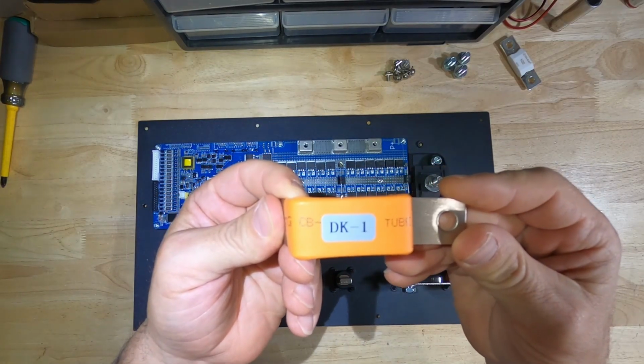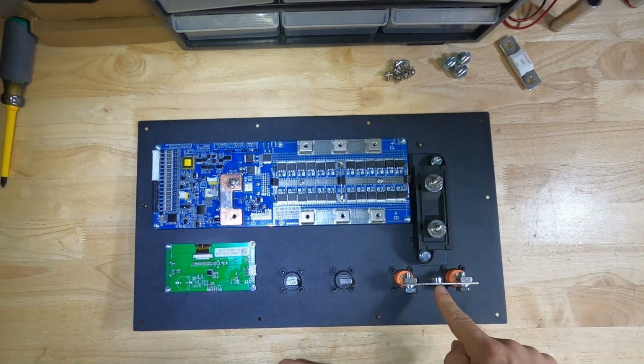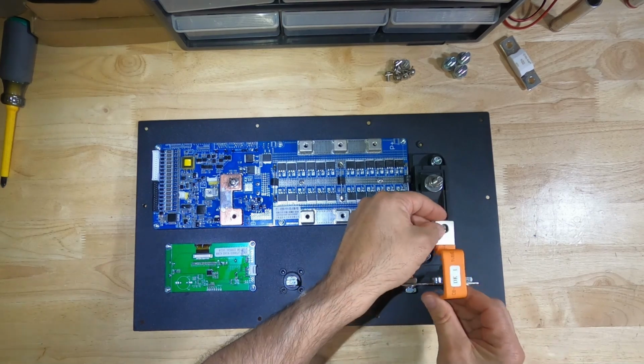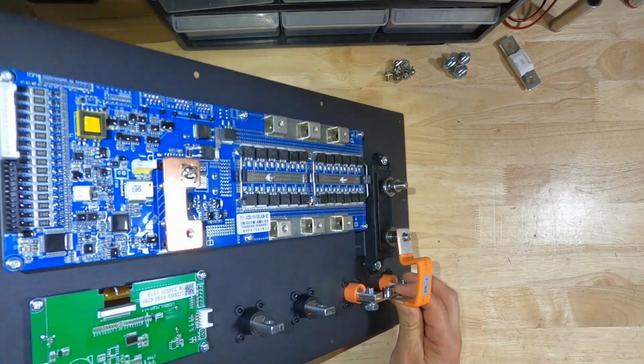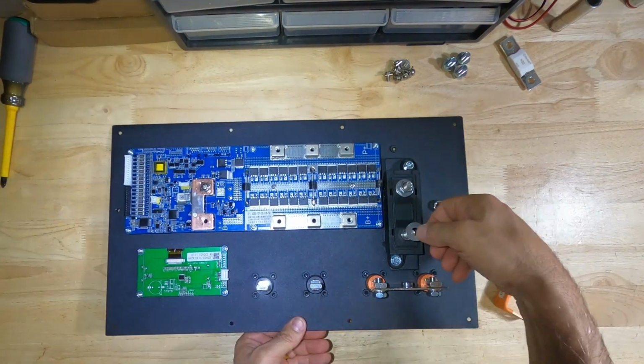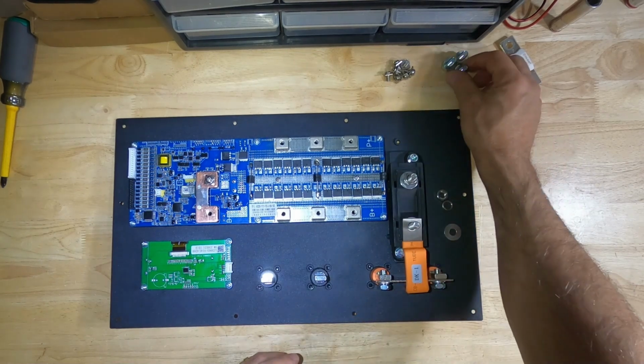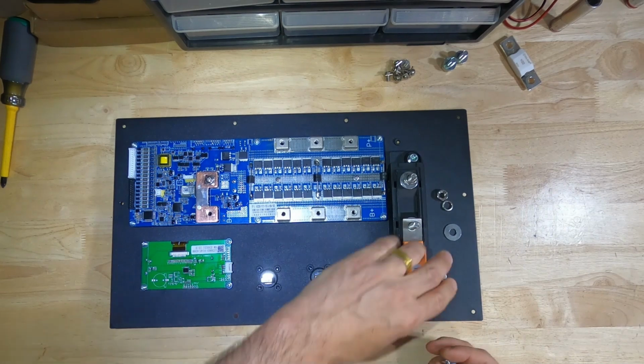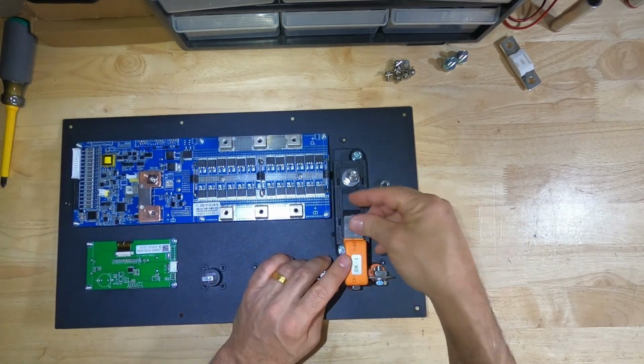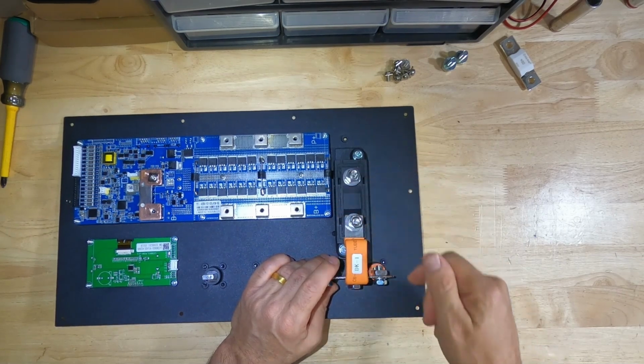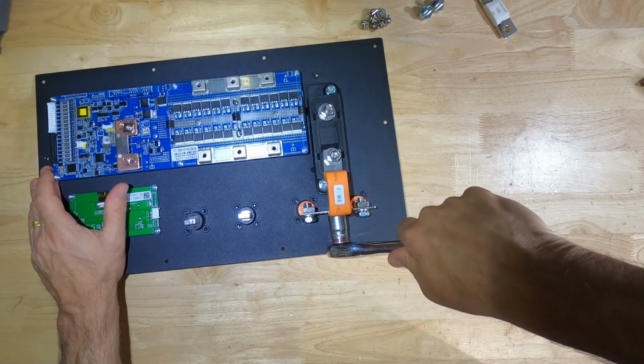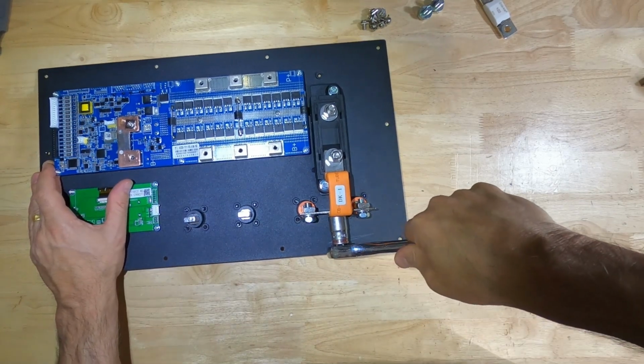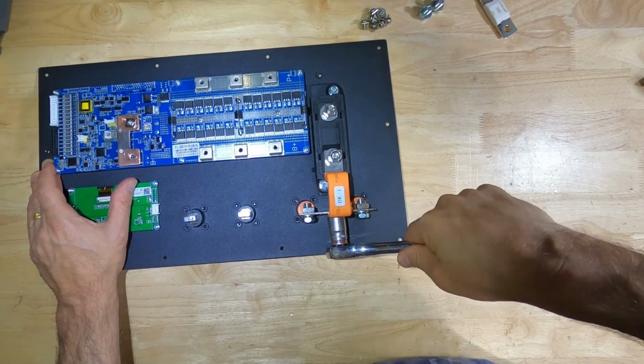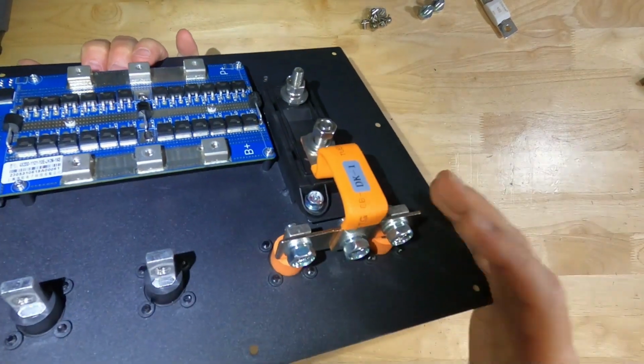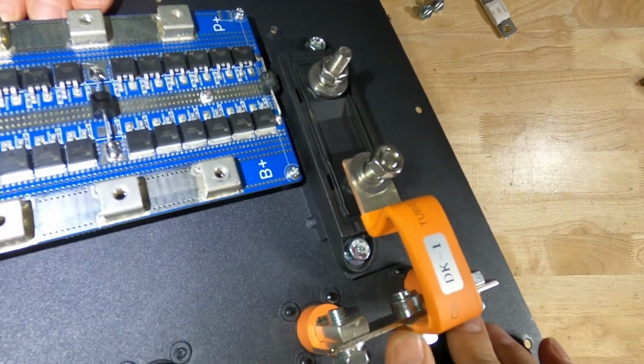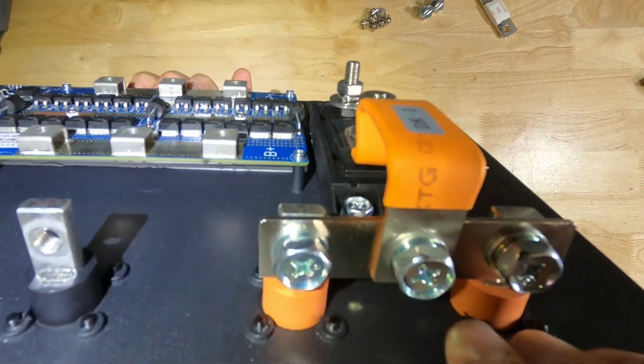Next we're going to install the DK1 jumper. It's going to go from here on the fuse over to our bridge, just like this. And again, we're going to use an M8 bolt. Perfect. Now the jumper is in direct contact with the bridge. That's how it should be.